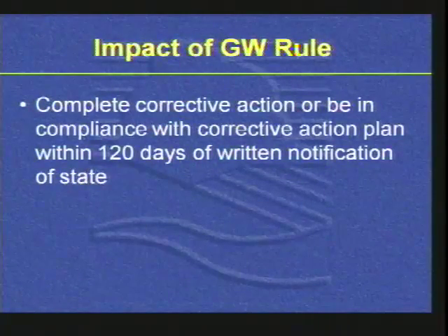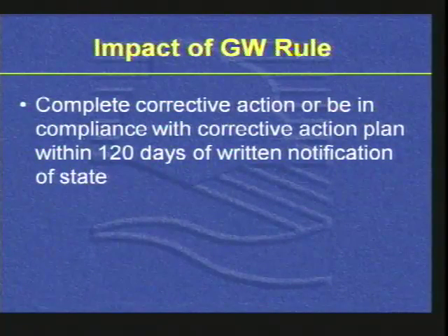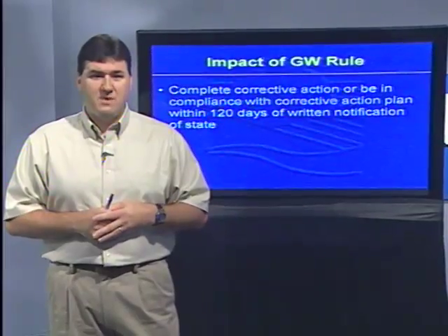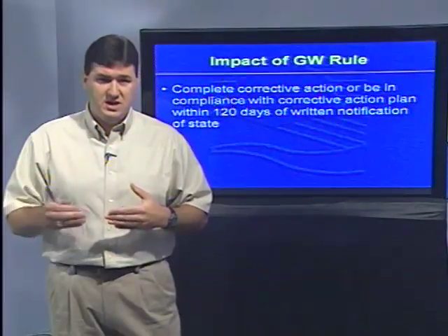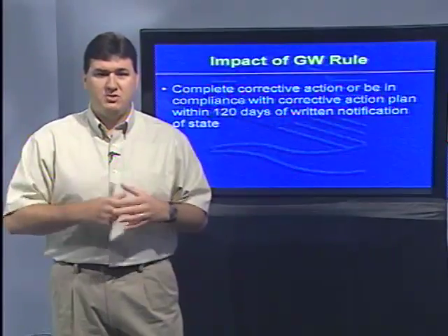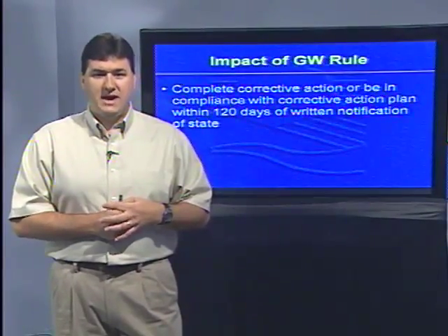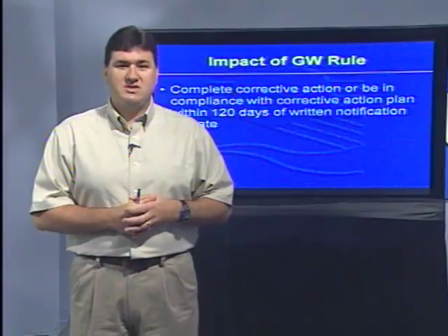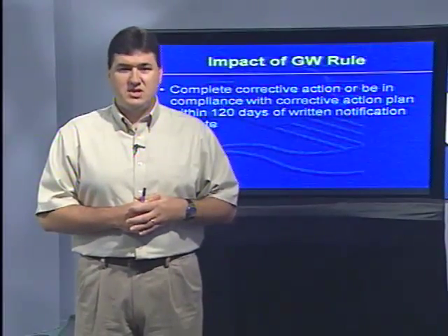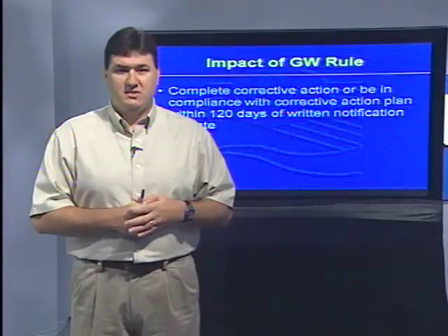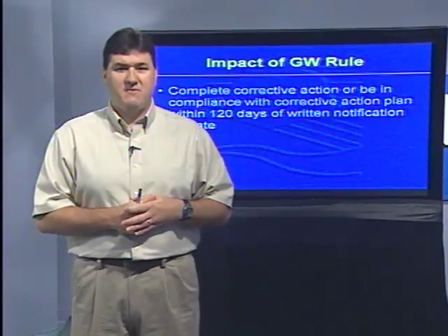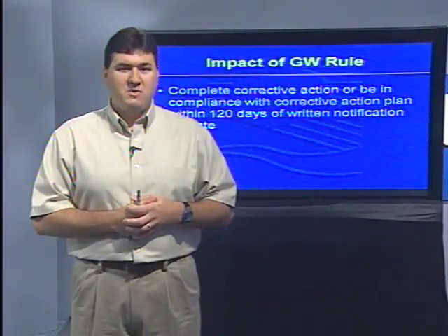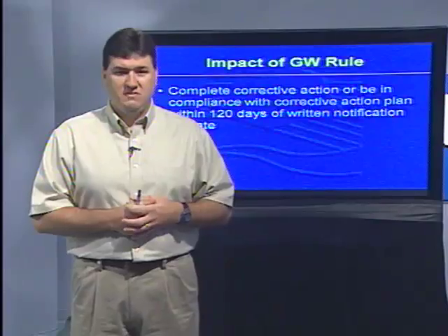Another component of the groundwater rule is to complete corrective action or be in compliance with the corrective action plan within 120 days of written notification. Depending on the significant deficiency, you can either correct the deficiency prior to 120 days or enter into a corrective action plan with the state. In Texas, we issue notices of violations describing the deficiency, specifying a corrective action and time frame, generally sent via certified mail.